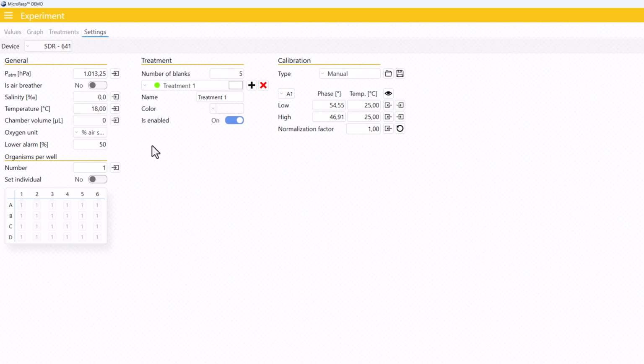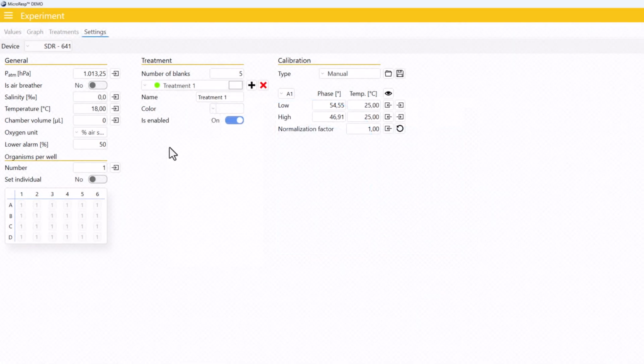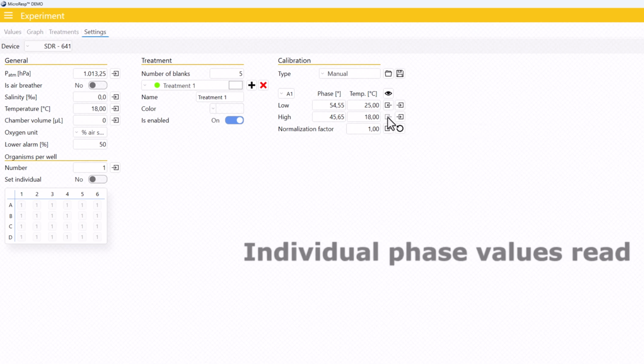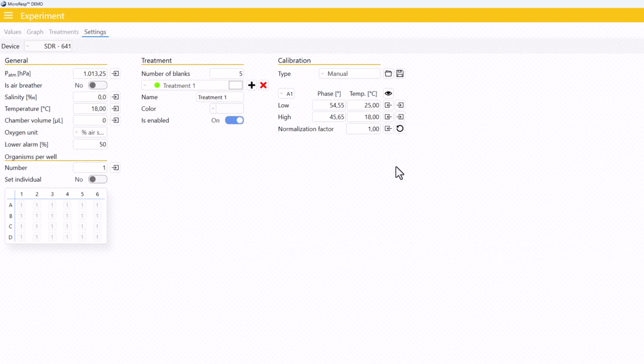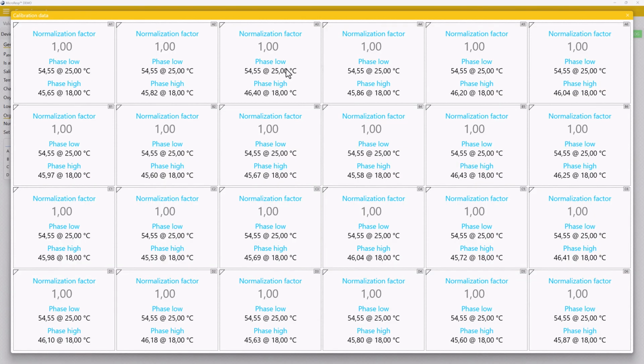Now fill the wells with the 100% air-saturated water sample. This mixed air-equilibrated water sample can be achieved by purging atmospheric air into the water sample, for example, using an air pump and air stone. Once the oxygen readings are stable, click the Read and Use phase and temperature values. The microplate reader will now read each oxygen sensor spot and transfer the data to MicroResp, and the calibration data can be seen using the eye icon here under the phase high for each well.